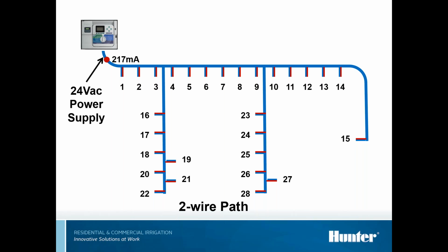With all those decoders, if you multiply those by a normal number, 7 3/4, you're going to have about 217. Now, this is going to be a typical system without problems right here. On the one that's all the way out, it's 7.75 because you're only reading one decoder. On that leg right there, the number of decoders right there times 7.75, and you get 47 milliamps. On the leg to the left that branches off, 54.